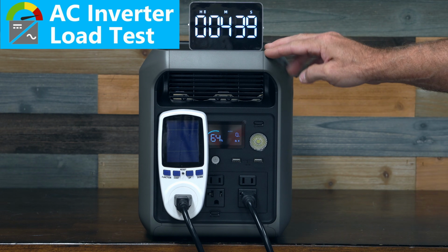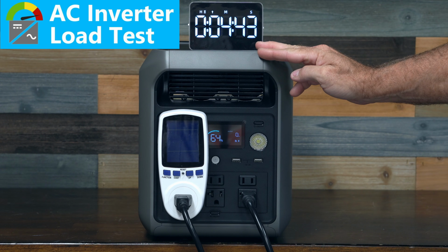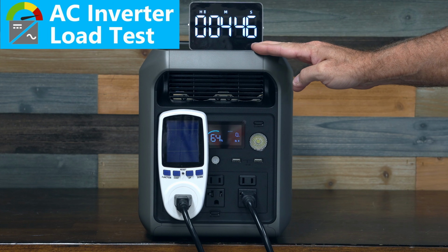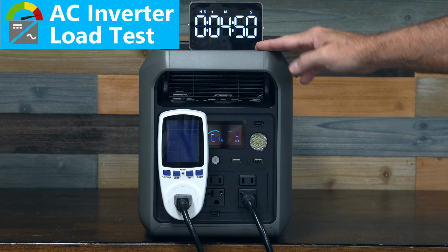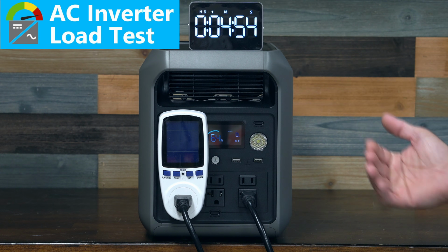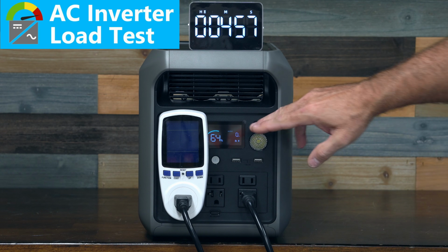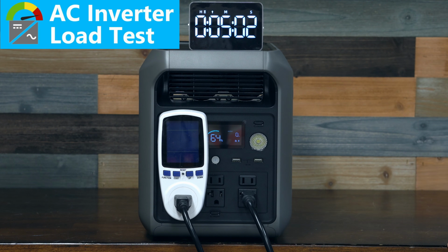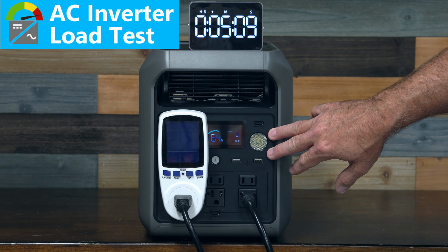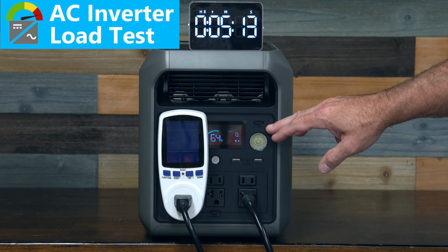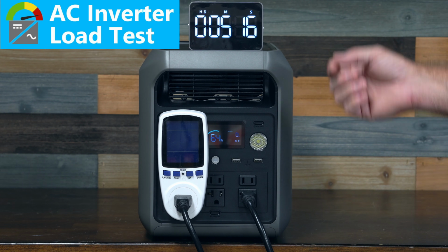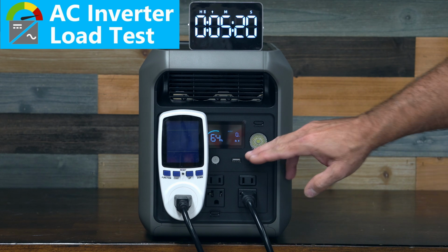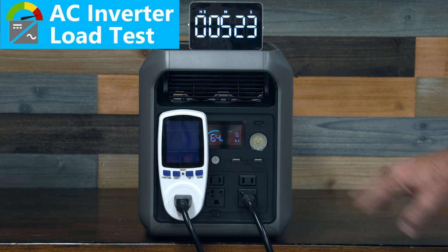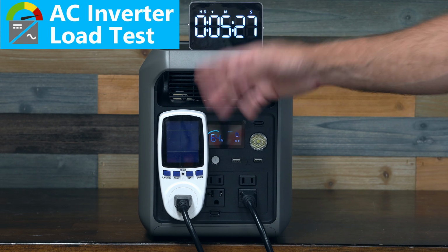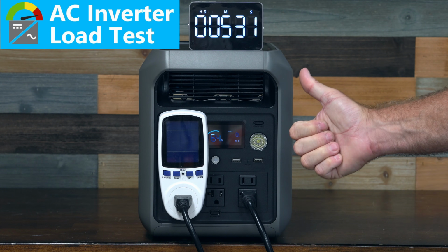The inverter load test is a definite pass. You can absolutely sustain 2200 watts and then some, probably a little more, maybe 2300 watts. But once you get just below 2400 watts, it will start cycling the voltage throttling on you, and it will regulate your power max at around 2200 to 2280 watts. That's how it behaves. You don't want to run complex electronics when it's voltage throttling, so if you're powering TVs, computers, or air conditioners, stay below that 2200 watt continuous load to avoid the throttling, and you'll get a nice full 120 volts. Very good load performance on this inverter.